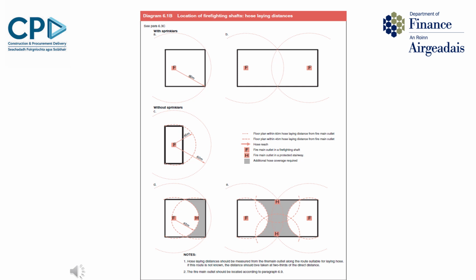Similarly for figure E on the larger floor plate, provision of two firefighting shafts as shown satisfies the first criteria of each part of the floor being within 60 metres of a fire main in a firefighting shaft. However, it doesn't meet the second criteria of each part of the floor being within 45 metres of a fire main. So the grey area is not covered, and a solution is to fit two additional protected stairways with a fire main outlet in each as indicated.